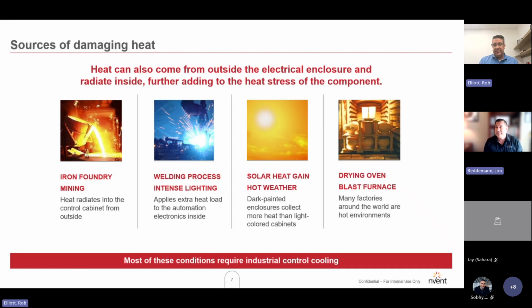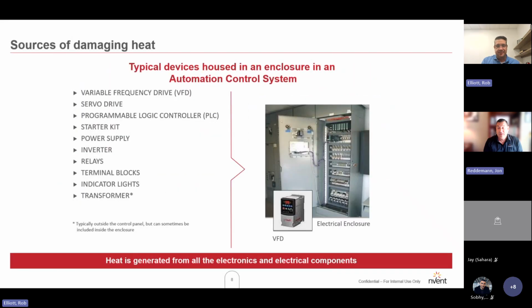Yeah, I was just thinking, my God, how many NEMA 3R enclosures have you seen out there driving along or out in a field as part of a process? Those are out there very often just baking, and standard NEMA 3R enclosures allow for that seepage at the bottom, but there's really not a whole lot of additional cooling that goes along with it that probably could definitely affect the process. Yeah, exactly. And an ANSI 61 gray enclosure in direct sunlight adds about 30 to 40% to the solar load of an enclosure as compared to a light colored or a white enclosure, which could definitely affect the overall sizing of a system, right?